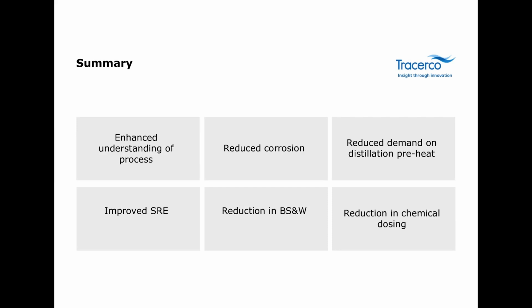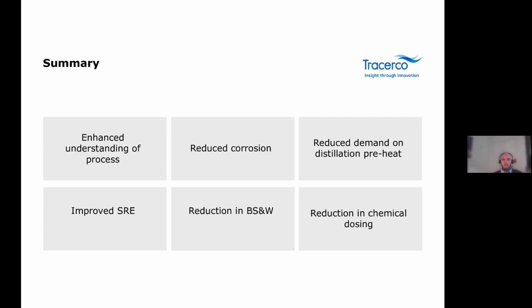So in the months after the installation of the profiler on the first stage desalter, a number of key and measurable benefits were realised that enhanced the unit's performance and reliability. Due to the industry-leading vertical resolution of 30mm, the client's confidence in the interface level was increased, which led to optimising the interface for maximum wash-water contact, reducing the emulsion breaker chemical dosing by 50%.